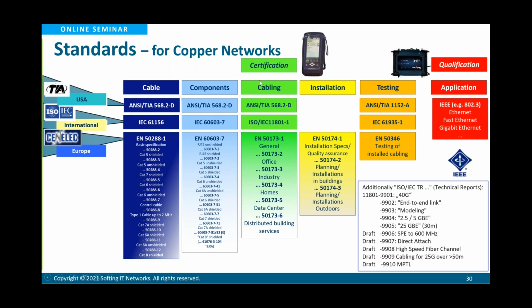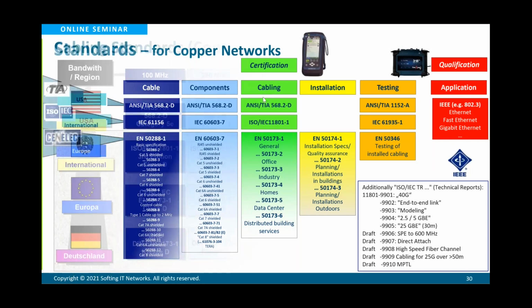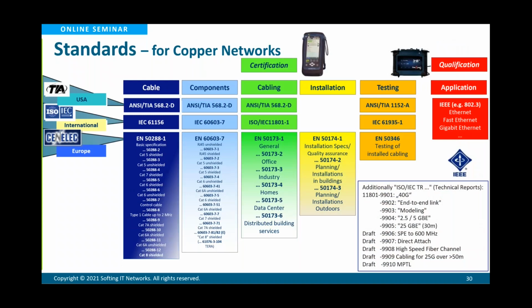Then you have the certification when the cabling is done. The cabling is certified according to the American standards from ANSI TIA 568.2-D. From the ISO IEC, it is the 11801-1. For the EN, it is the 50173-1 in general, -2 for office, -3 for industry, -4 for homes, -5 for data center, and -6 for distributed building services.